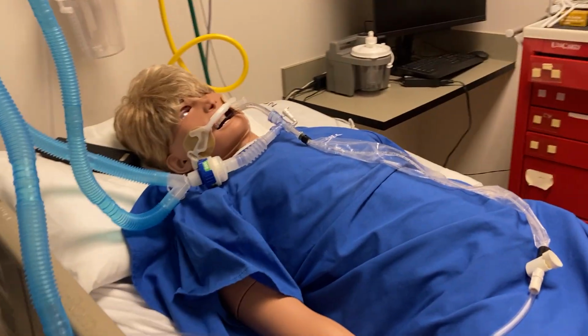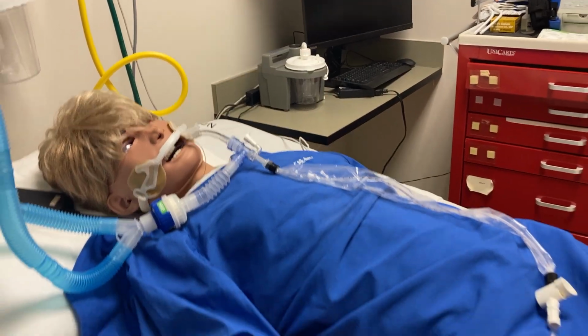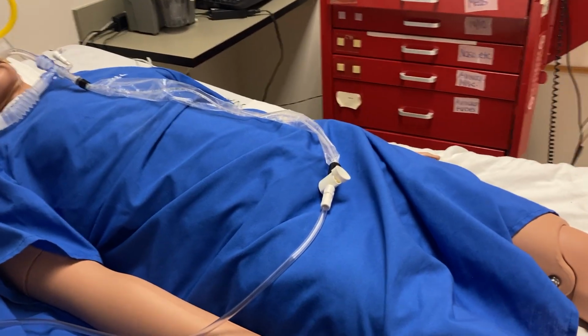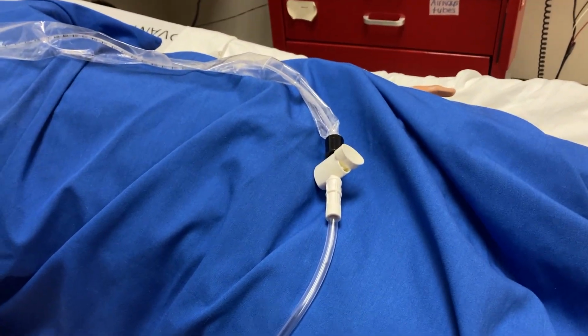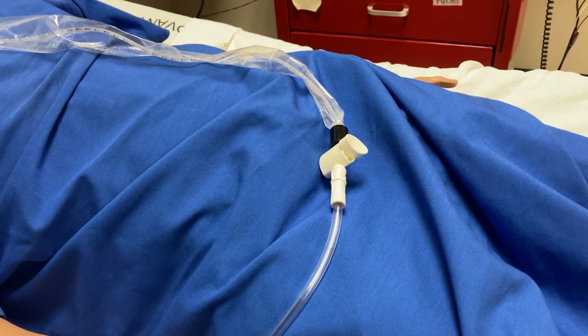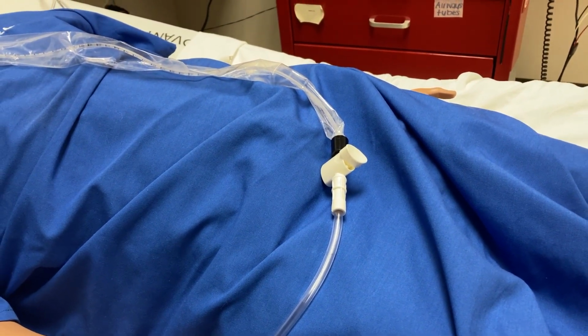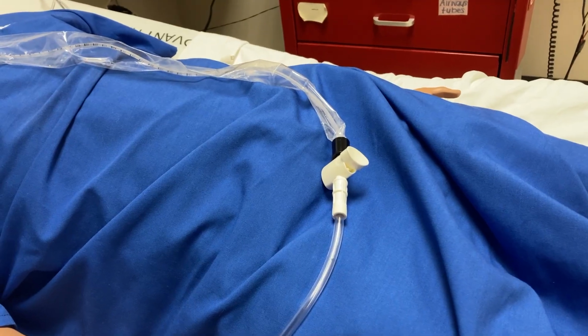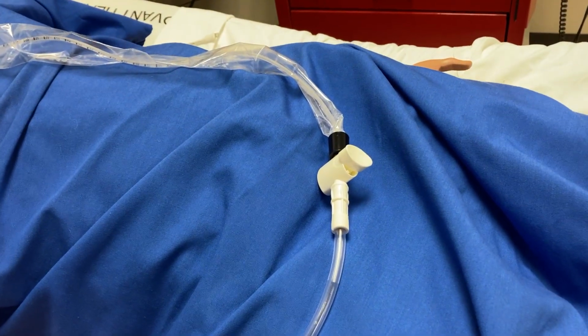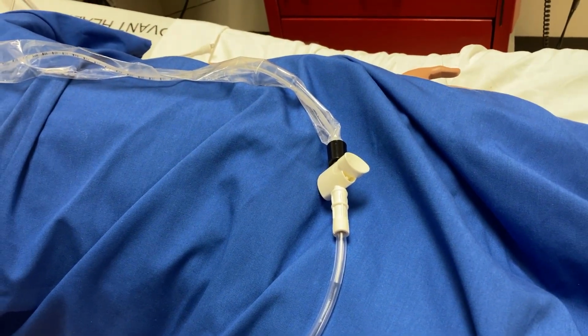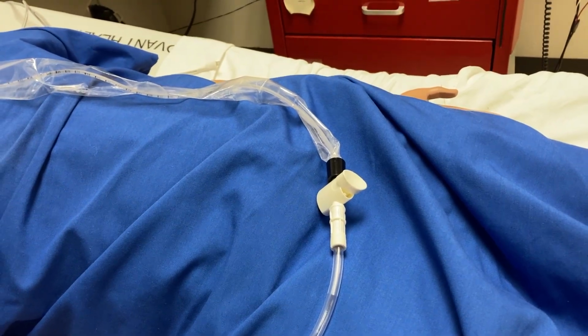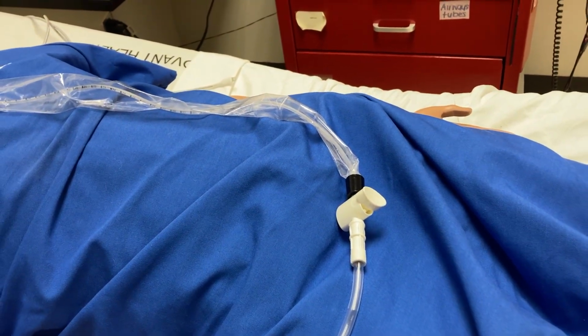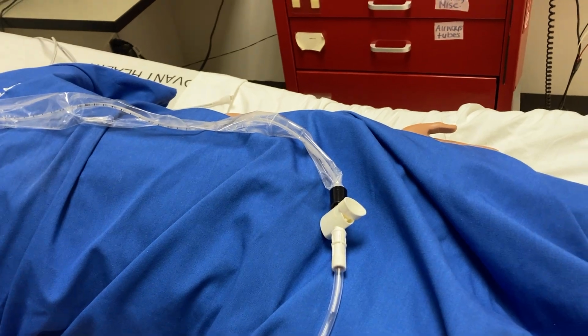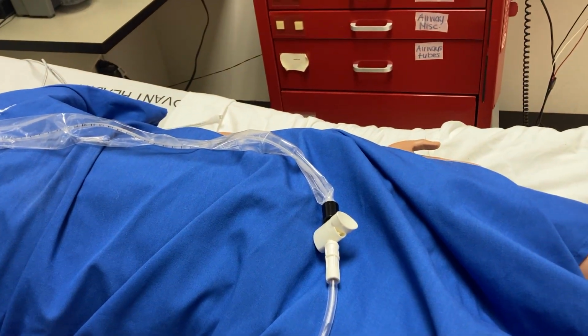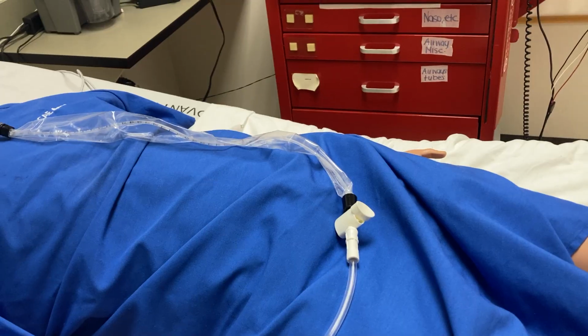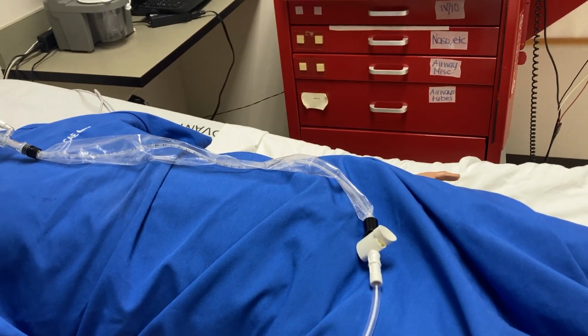Would also note that the suction catheter, the way that it's set up here, is locked. However, we teach our students to make sure that it is in its collar in the locked position, because if the patient were to be rolled or what have you inadvertently, that could be clicked over into the unlocked position, which if that were to be depressed, then that could cause an issue with pulling out some of the volume from the ventilator as it's being delivered.